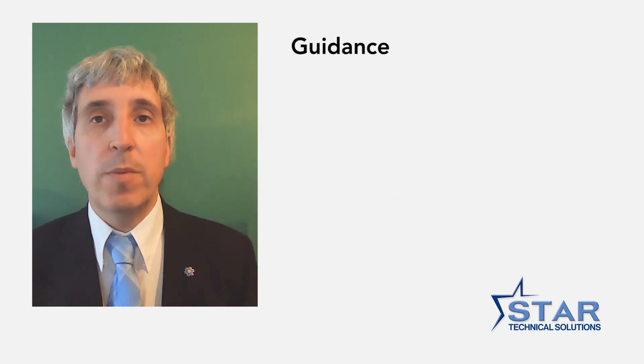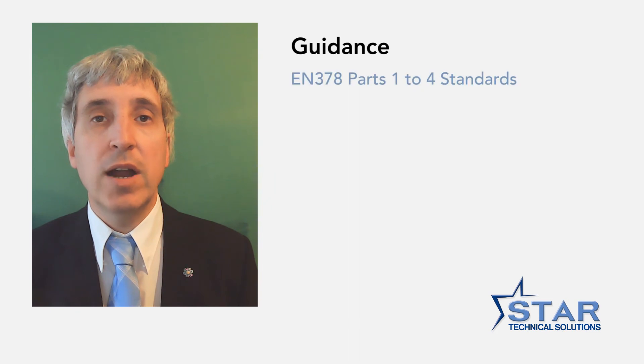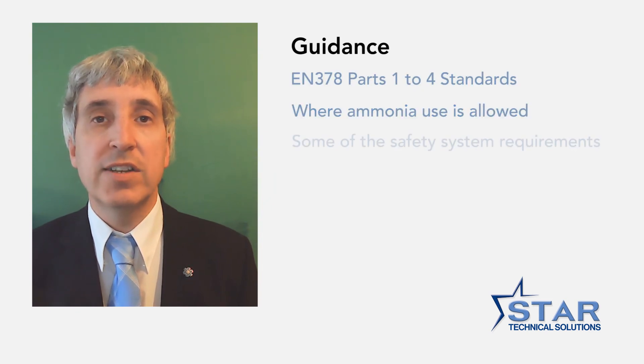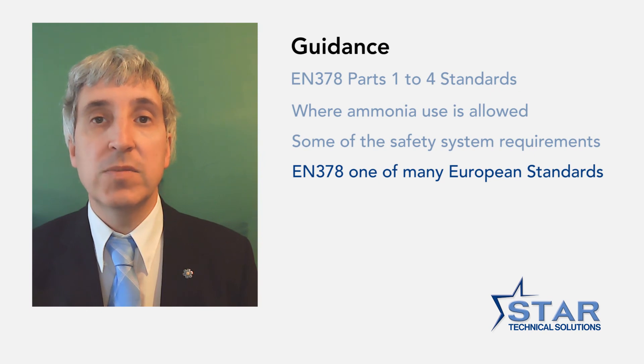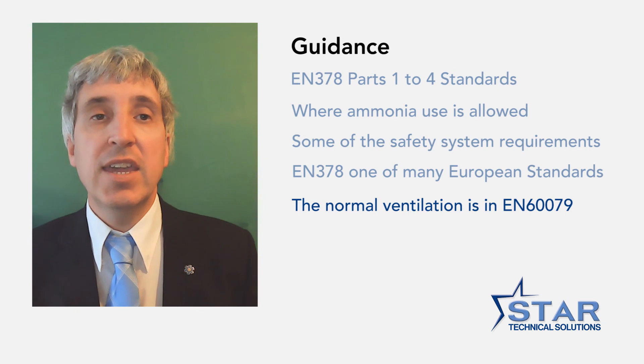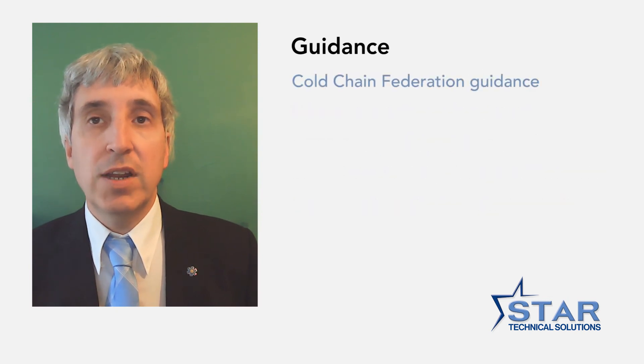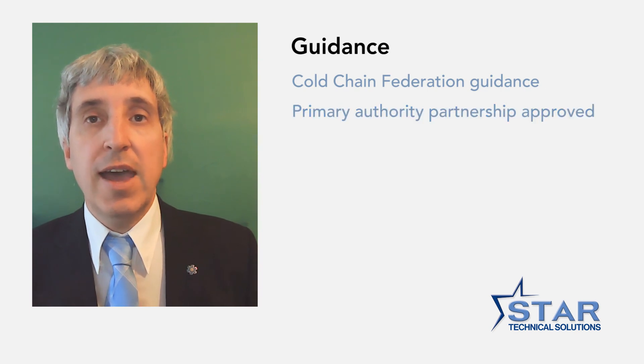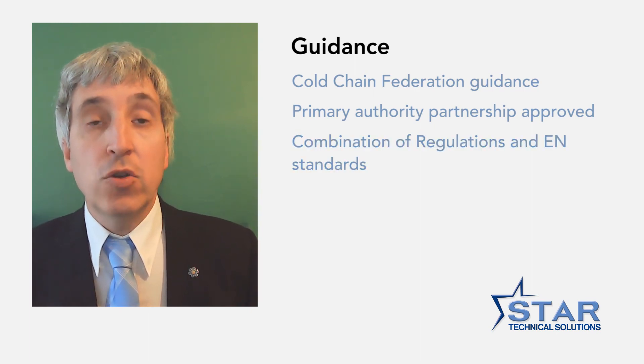Whilst the regulations give the broad requirement that equipment in the workplace should be safe, there is also industry guidance. The European and UK recognised published guidance is EN 378, which has four parts. The EN 378 standards are very broad and focus on the design of refrigeration systems, detailing where and where not ammonia use is allowed and providing some of the requirements of the safety systems. However, EN 378 is only one of many European standards for refrigeration systems. For example, EN 378 does not deal with the normal ventilation requirements for ammonia systems and points to other European standards EN 60079 for classification of places. The Cold Chain Federation has produced ammonia guidance for the industry and its primary authority partnership approved guidance combines the UK regulatory requirements and European guidance. The guidance documents are free of charge and are available on the Cold Chain Federation website.